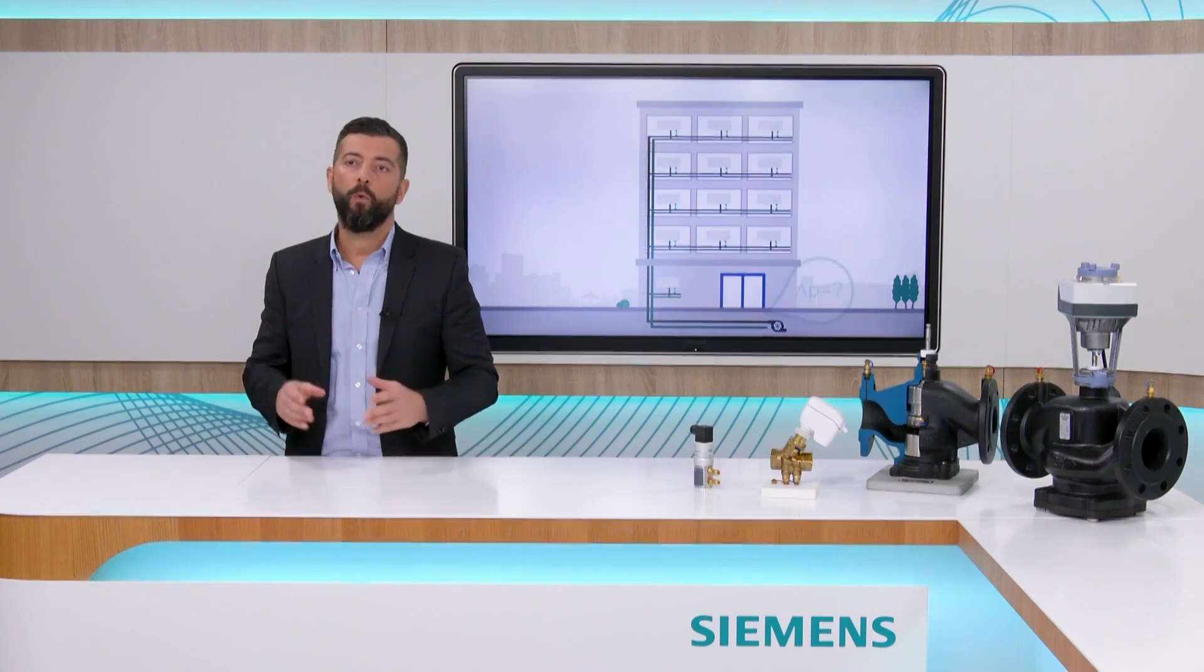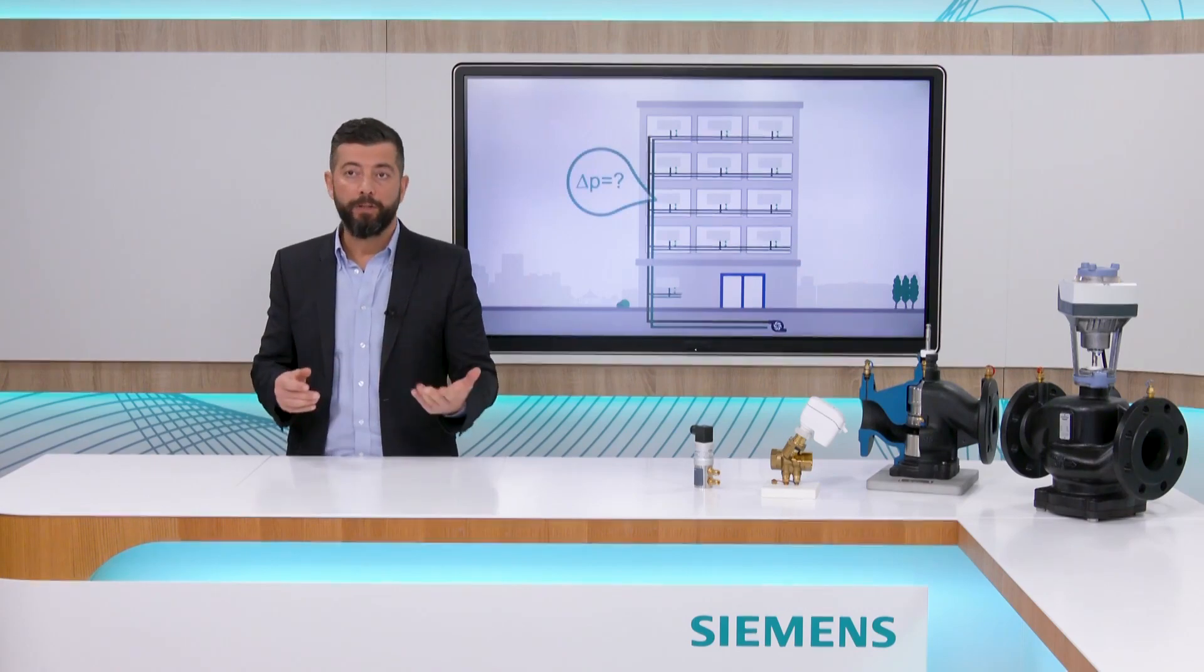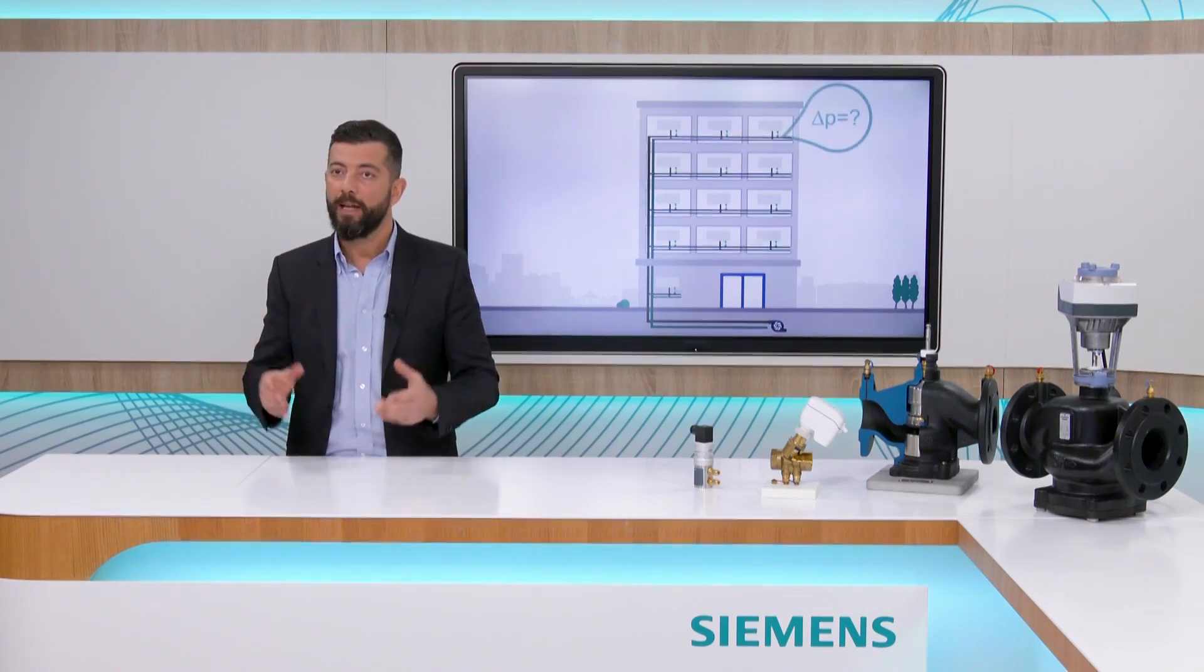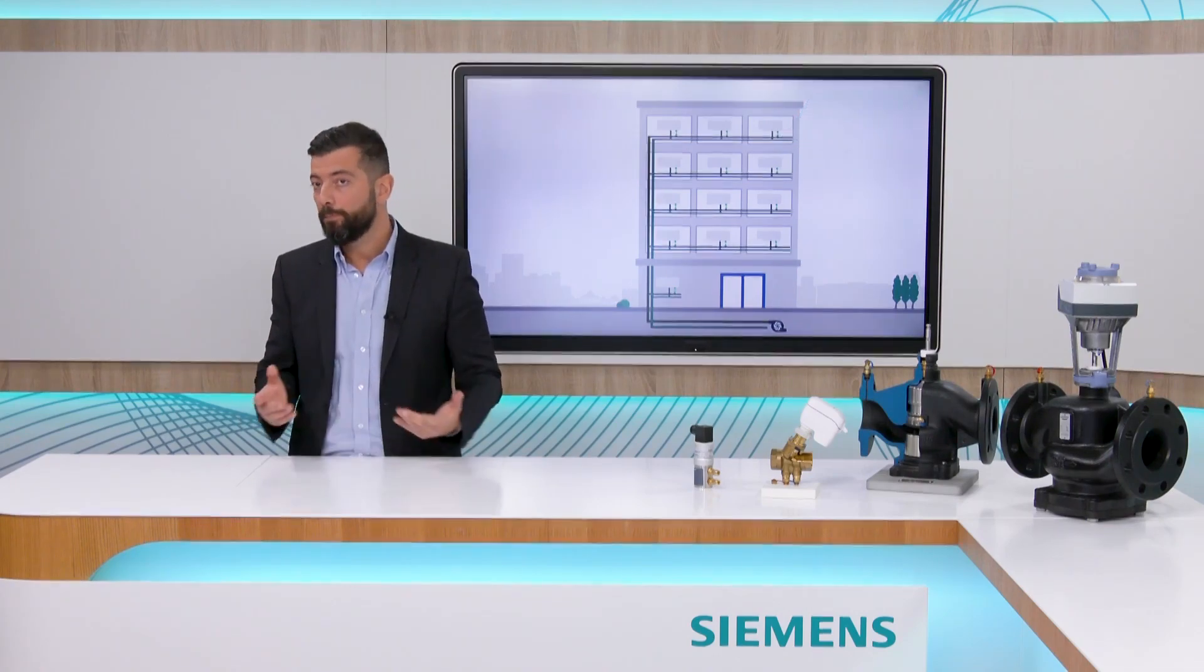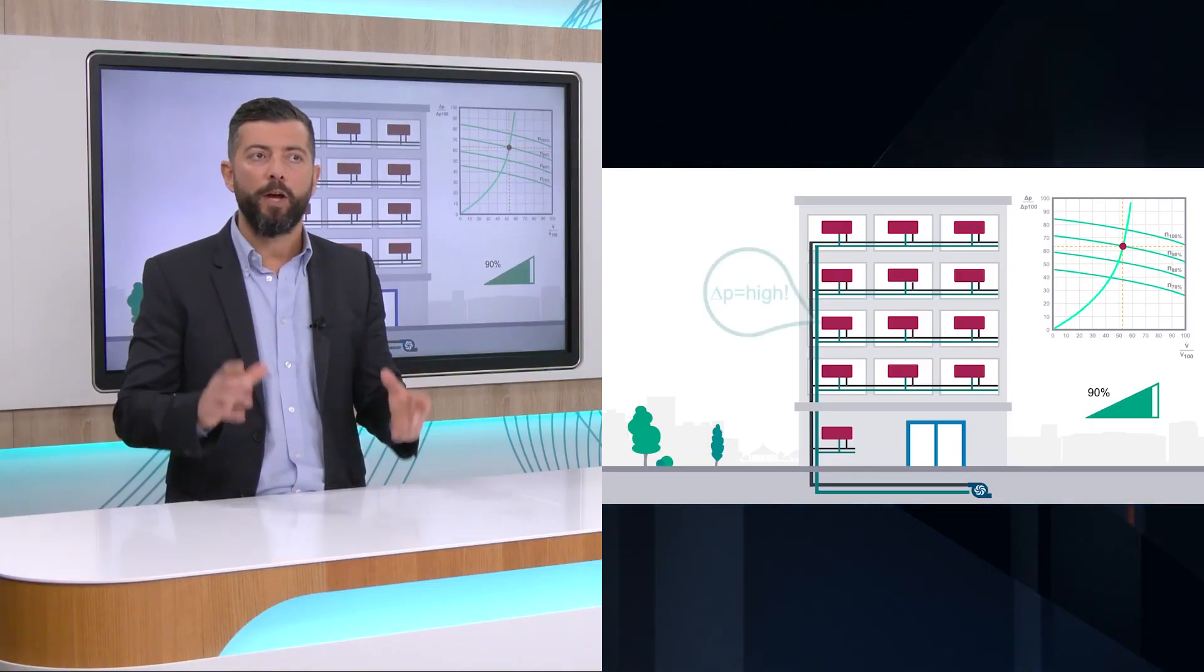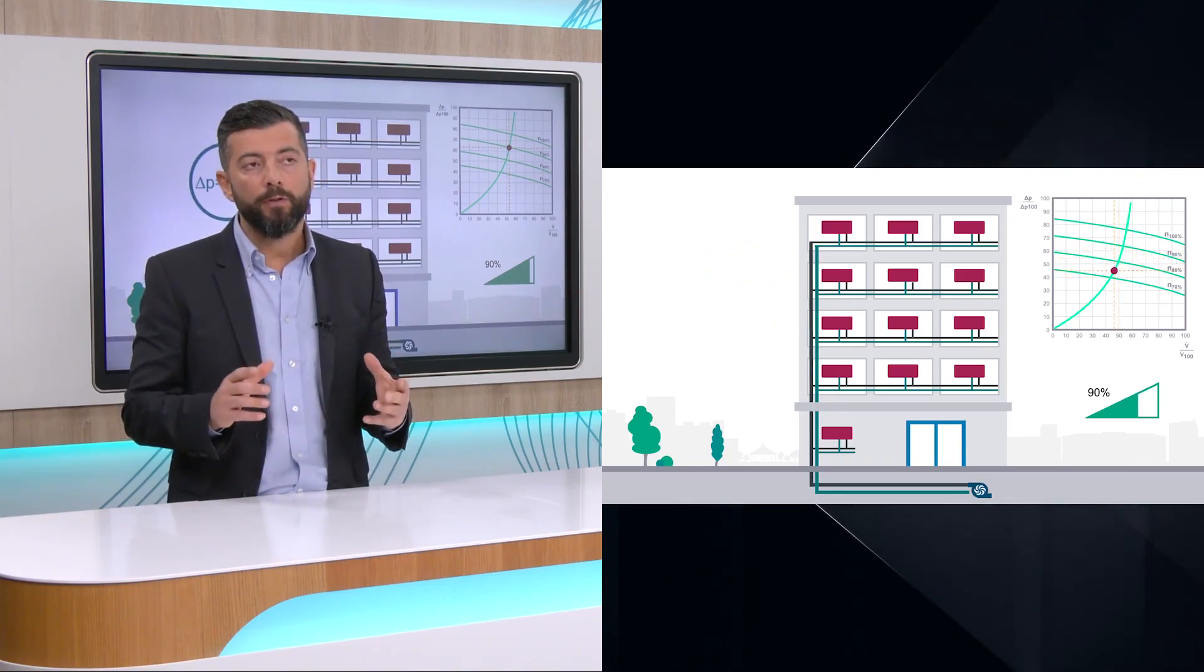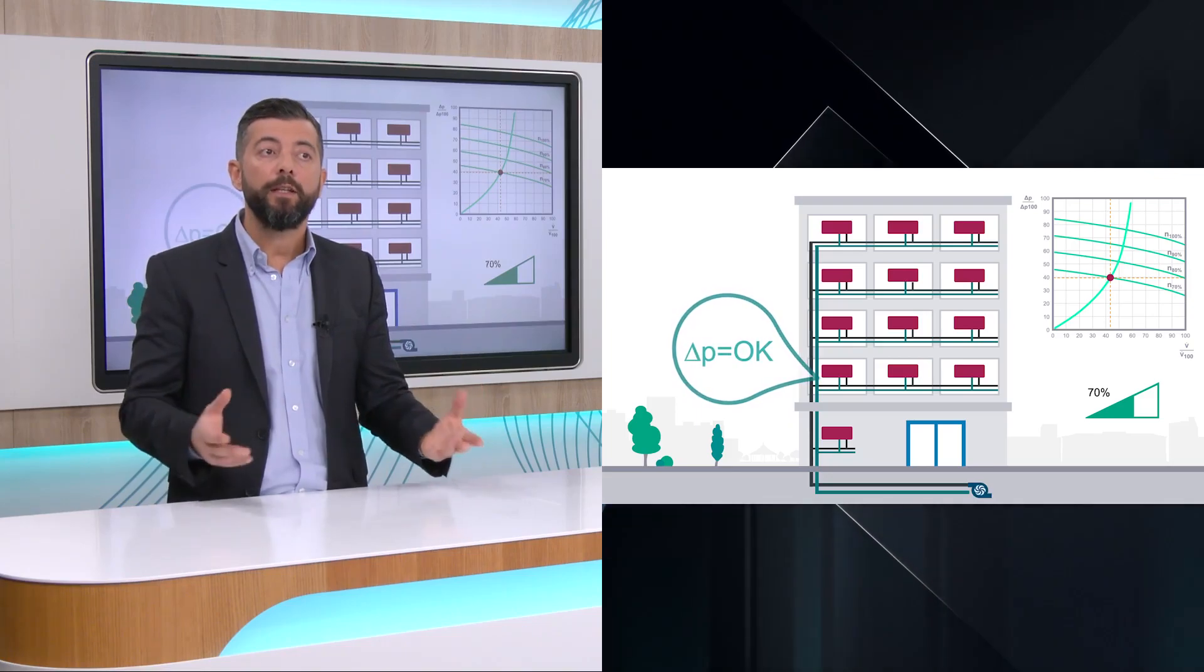In order to do this, one must check the available differential pressure delivered by the pump in different parts of the system and especially make sure there is enough pressure available at the most remote terminal units. These parts are called the index circuits. In case of too much pressure there, the pump maximum speed can be reduced and further adjustments can be made until an ideal setting is reached.